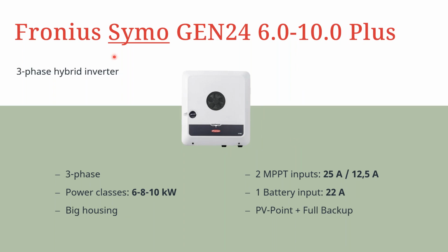Then the bigger Symo GEN24 Plus, which is the power class 6, 8, and 10 kilowatts. This comes in a bigger housing. For the 2 MPPTs, we have 25 amps and 12 amps. So we can see here, similar to the Primo GEN24, the bigger Symo GEN24 has a higher current handling capacity for MPPT 1 compared to MPPT number 2. And for the battery input, we have a maximum current of 22 amps. Therefore, this means that the Symo GEN24 6, 8, and 10 kilowatts can provide you with both the PV point and full backup. This full backup is only possible with a battery connection.